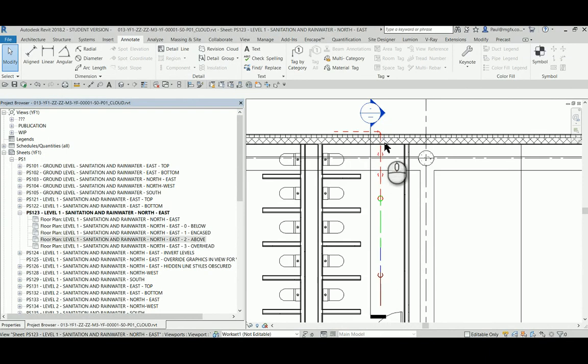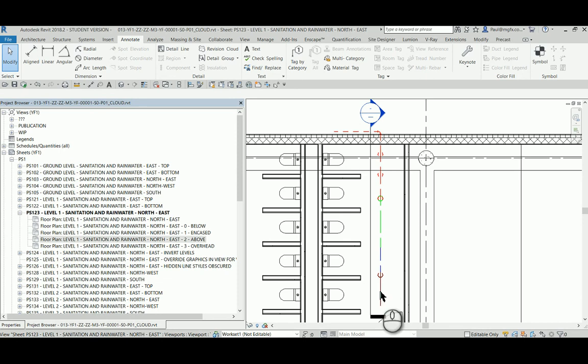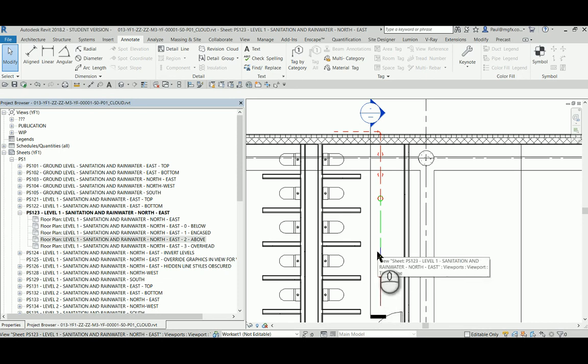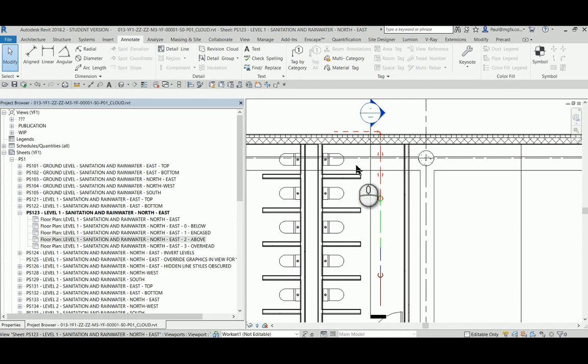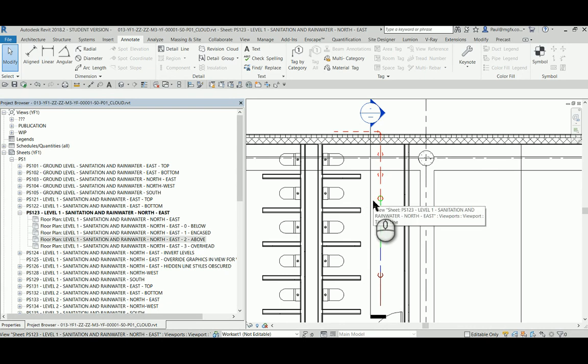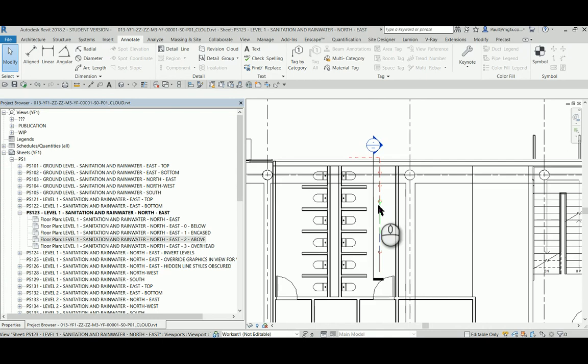Showing how one pipe may be shown up in different colors depending on whether it's overhead, within the level, encased in the floor below, or running below the floor. Now clearly this will have limitations - one would have to be on a very horizontal floor. It wouldn't necessarily apply to a sloped floor or to a stepped floor, in which case one might have to resort to more views and superimpose them as well.